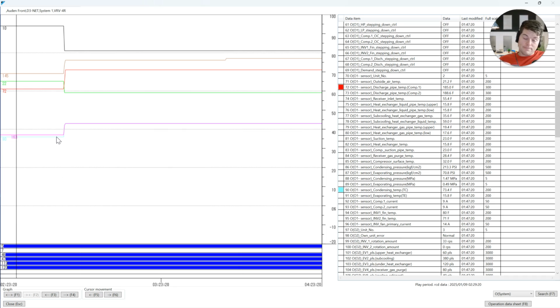So oil return mode. It serves a purpose. It's a great tool. It's a great application. It is not a design flaw, before those of you who are going to jump to conclusions. If you install it correctly and you charge it correctly and you maintain it correctly, oil return is a beautiful thing. Now, when the charge is off, the line sizes are the wrong size, the system is dirty, and the coils are dirty, and it goes into oil return, unfortunately, it does kill compressors.